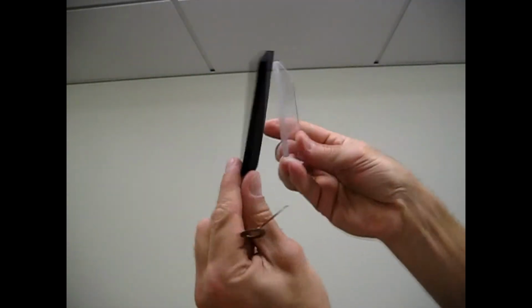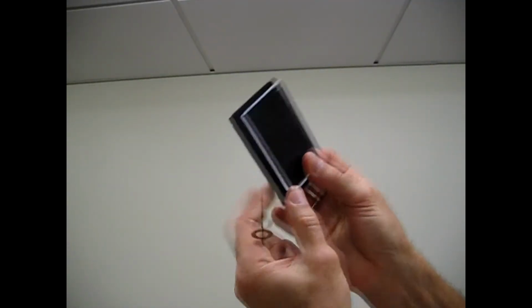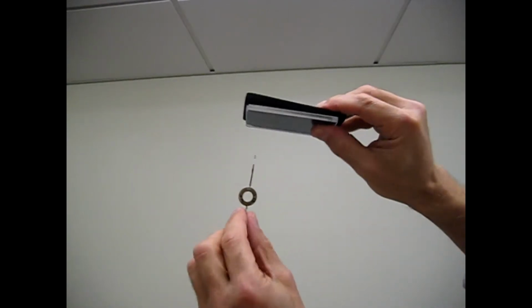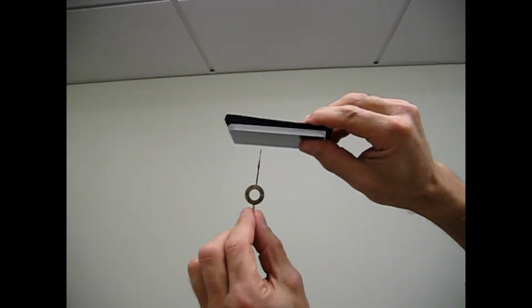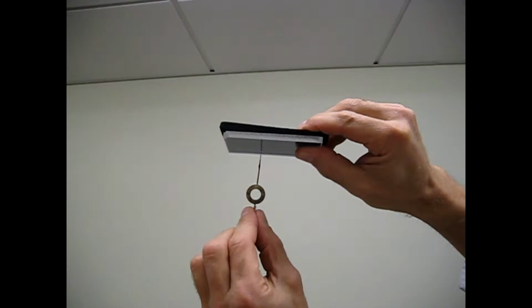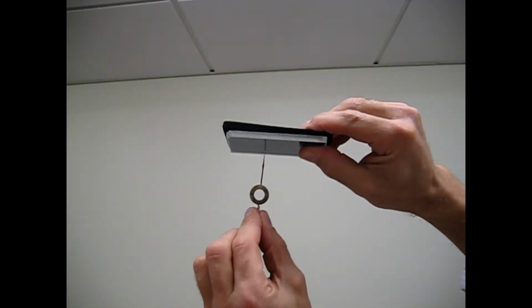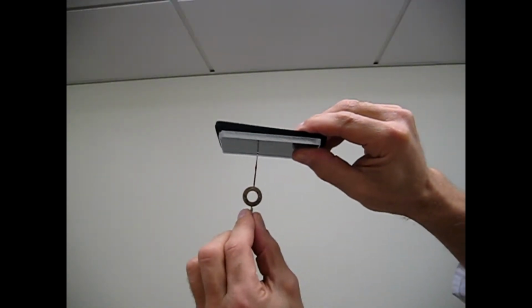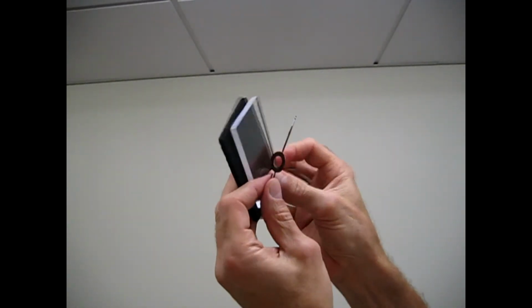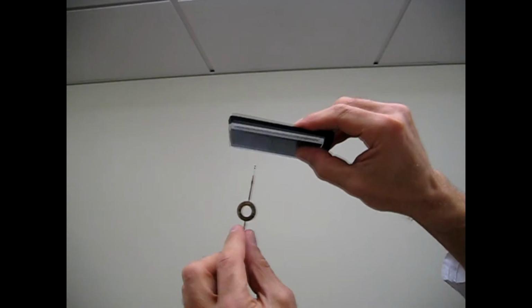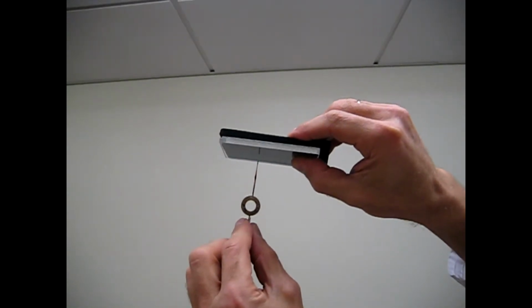In difference from the teletherapy water phantom, where we used the water surface as a mirror to reflect the empty device, in the brachytherapy phantom the mirror for reflection of the empty device is the lower surface of a plastic plate. All distances are counted from this surface. It plays the role of zero coordinate.